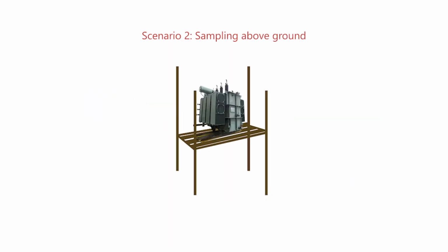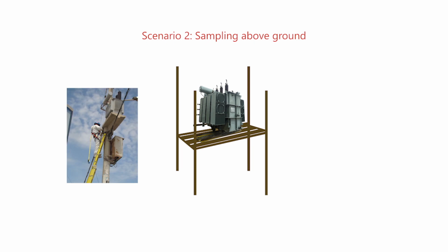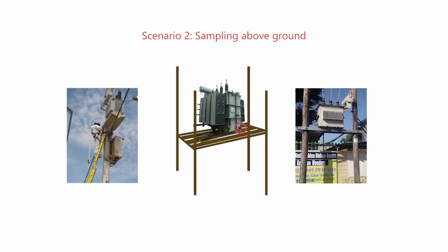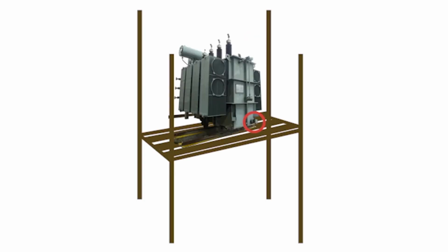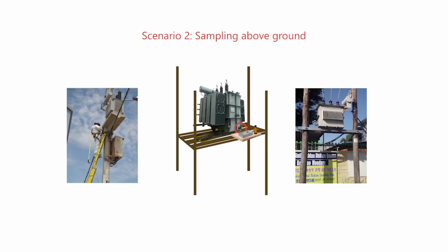As some transformers might be located above ground, a fiberglass ladder and harness will be needed to reach the drain valve. For this scenario, and when we do not have a platform to place the spill tray, it will be important to have a piece of wood or plastic at hand to place under the drain valve in order to be able to place the spill tray and the sample bottle on it.